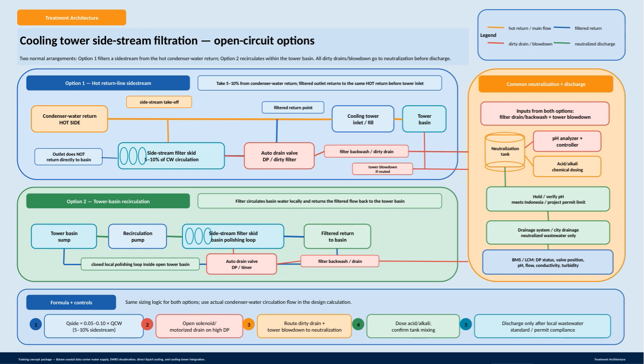Option 2 uses a closed local polishing loop within the cooling tower basin itself. In this arrangement, basin water is circulated through the filter and then returned back to the basin. This approach continuously cleans the water inside the tower while keeping the system closed locally. For both options, all dirty drains and blowdown water are routed through a neutralization process before discharge. This includes a filter backwash and tower blowdown, which enter a neutralization tank, where pH is carefully monitored and controlled using acid or alkali dosing to meet the local wastewater discharge standards. The neutralized wastewater is then safely discharged to the city drainage system.